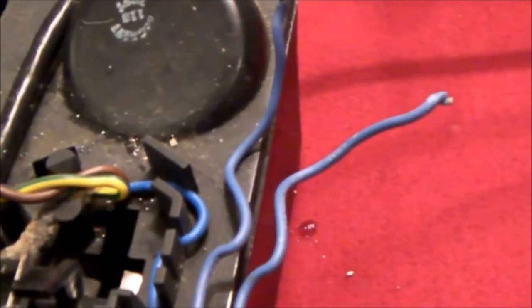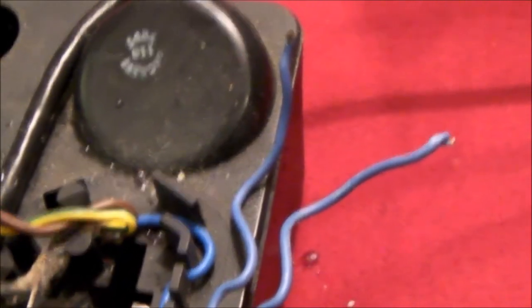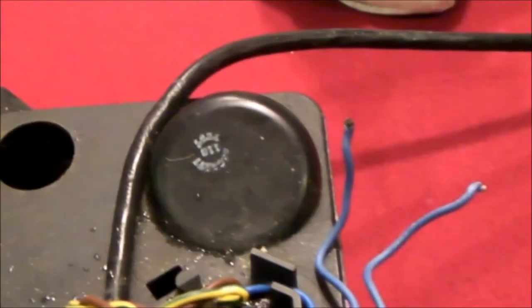And then this auxiliary switch is wired in series with your control circuit to your furnace and air handler. So if the condensate pump is full of water, it doesn't allow the air conditioning or high-efficiency furnace to create any more water until you resolve this problem.